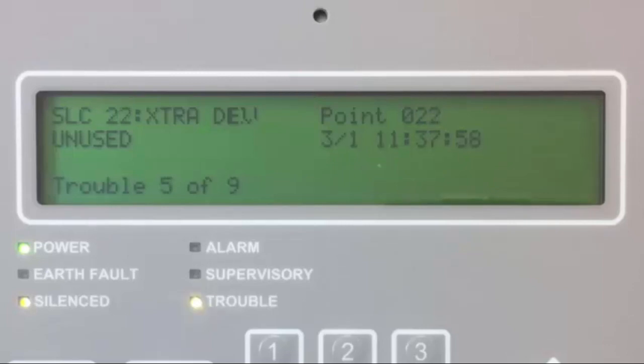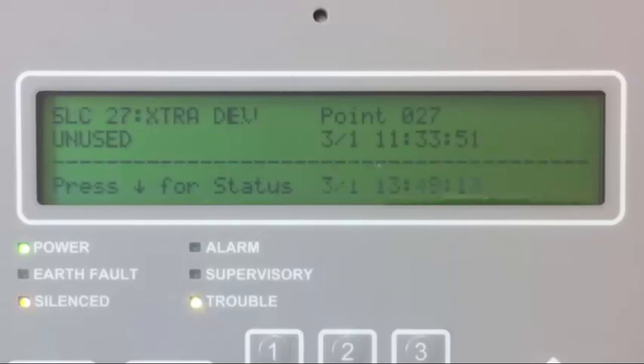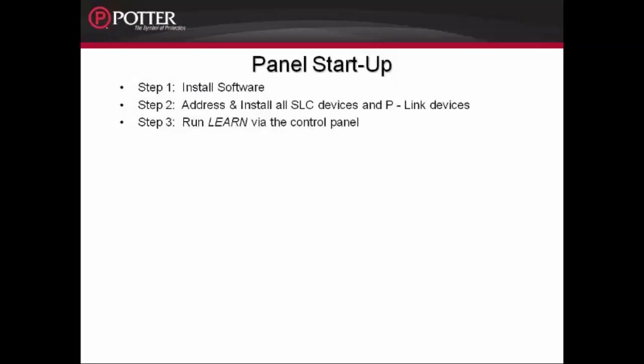If, for example, you've installed 9 devices on your SLC circuit and you only see 7 troubles, we already know that there's a problem with the installation. Once that step is accomplished, we can move on to Step 3.